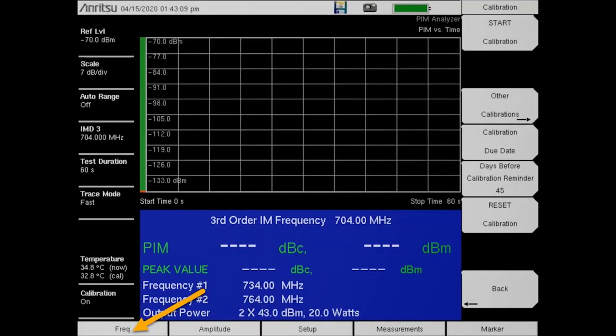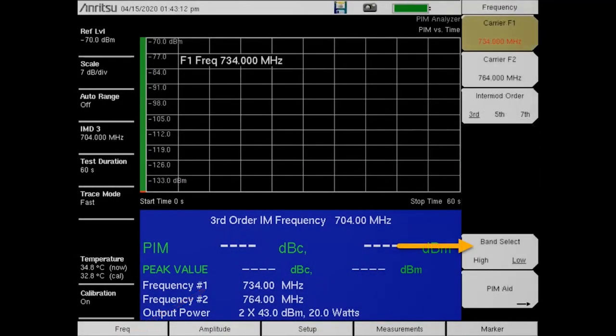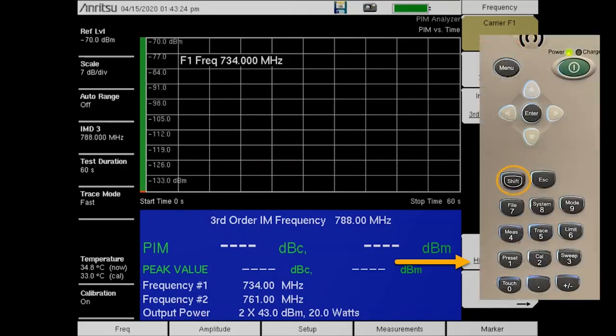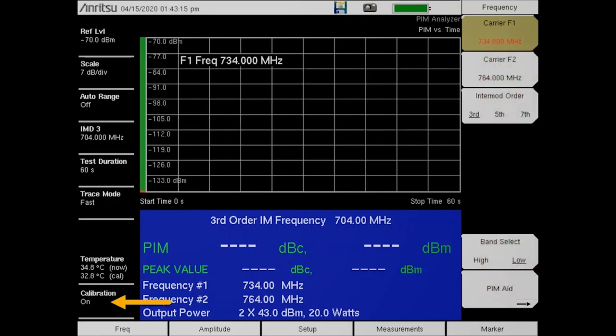Press the Freq button, followed by Band Select. Be sure the high option is underlined. Finally, repeat the calibration process. Once both calibrations are complete, Calibration On will be indicated at the lower left side of the screen, and you are now able to switch back and forth between the two IM test frequencies without recalibrating.